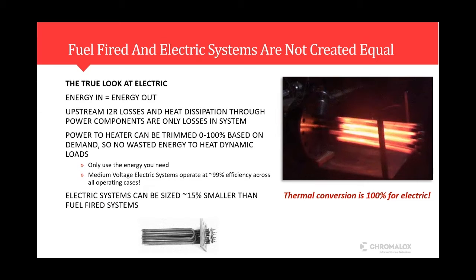So what that means is the ability to convert all that applied energy into heat, and the ability to control these electric systems on a 0 to 100 basis means we can use exactly the heat that we need. And typically that translates into a reduction in size of about 15% on average. So that's why in the title I put that fuel-fired and electric systems are not created equal, because often we're looking at those studies where a 3 megawatt electric system is compared to a 3 megawatt gas-fired system. In reality, that's not what we see in the real world. We know that these systems respond much better and are much more efficient, so we can actually have a smaller electric system than what the gas-fired counterpart might be.